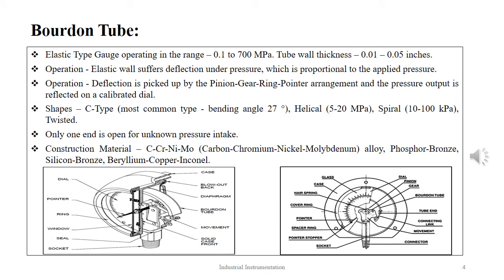The Bourdon tube is an elastic type pressure gauge which experiences deflection under pressure. The measurement range of the Bourdon tube is 0.1 to 700 megapascal. The tube walls have a thickness between 0.01 and 0.05 inches. This deflection is a function of the applied pressure. It is a fixed device having an opening at one end through which the unknown pressure is applied. The construction is elliptical in shape, bent in the shape of a semicircular arc, quite like the alphabet C, generally termed as C-type Bourdon tube.